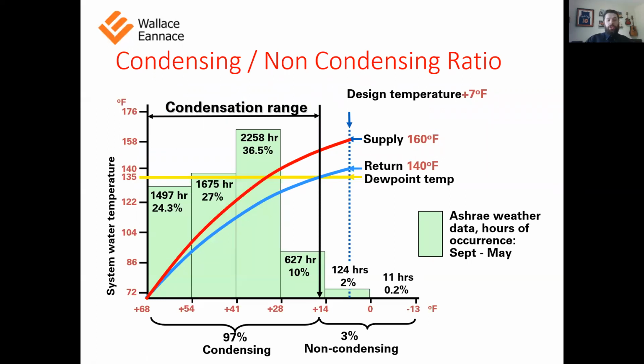So this is a chart here. I just want to show you guys how you get condensing. Basically, the best way to get condensing is the low return temperature. So 140 degrees and under is sort of your dew point where you're going to get condensing. When you get into condensing, that's when you're getting up into that 92, 93, 94, 96% efficiency when your boiler's condensing like that. So we do that using an outdoor reset. This chart can show you that on a cooler day, you can lower your outgoing temperature so that your return temperature is lower. Make sure you get that nice, good condensing, okay?